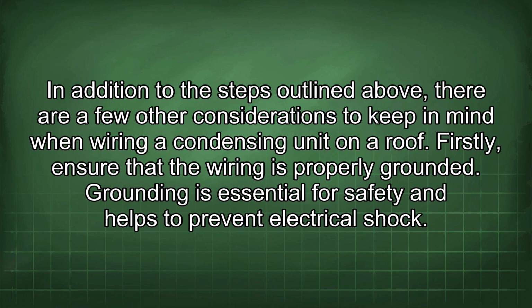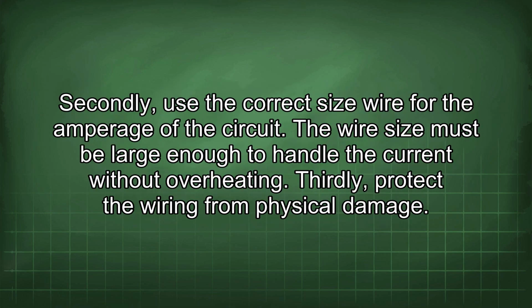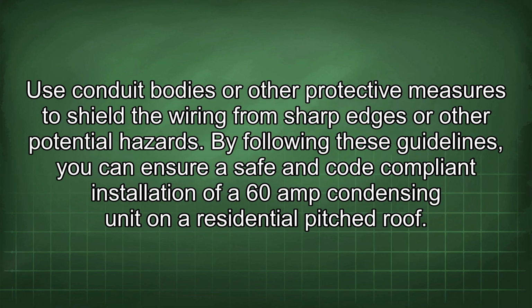Firstly, ensure that the wiring is properly grounded. Grounding is essential for safety and helps to prevent electrical shock. Secondly, use the correct size wire for the amperage of the circuit. The wire size must be large enough to handle the current without overheating. Thirdly, protect the wiring from physical damage. Use conduit bodies or other protective measures to shield the wiring from sharp edges or other potential hazards.